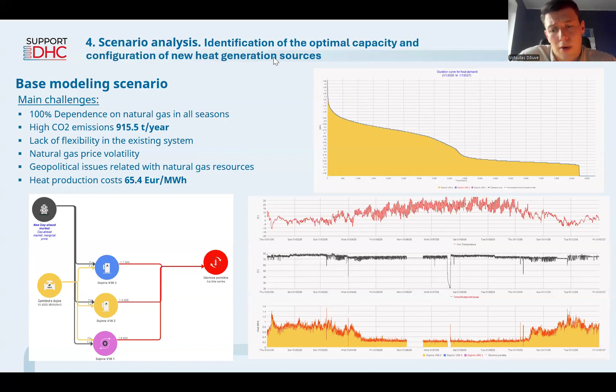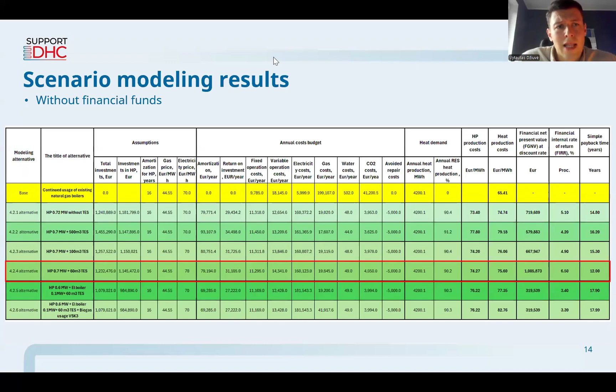Despite this fact, a comprehensive scenario analysis was implemented with 6 scenarios by sizing different capacities of heat pumps with different sizes of short-term storage. The analysis showed that the most optimal option might be alternative number 4, incorporating a heat pump sized at 0.7 megawatts with a 60 cubic meter short-term storage, allowing a very fast, simple payback time.